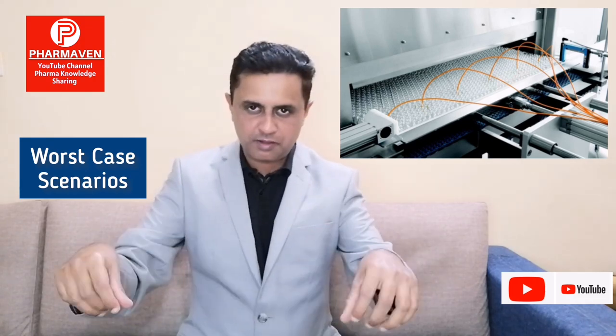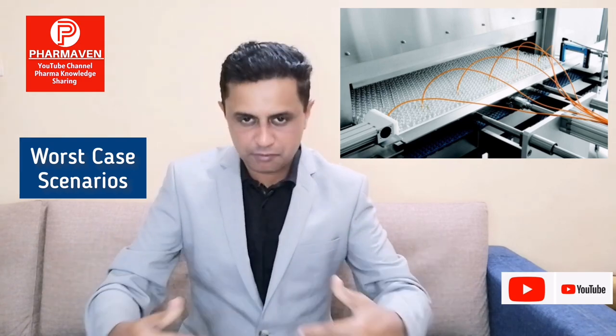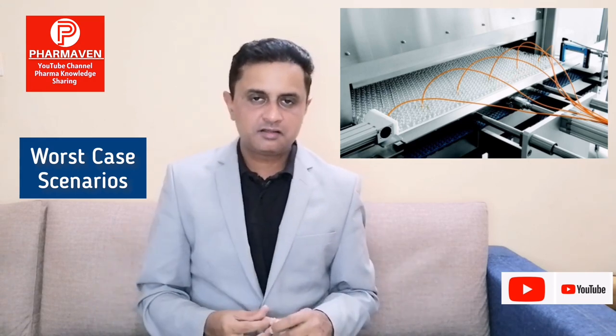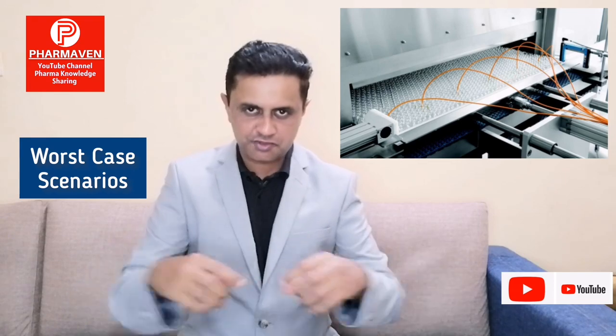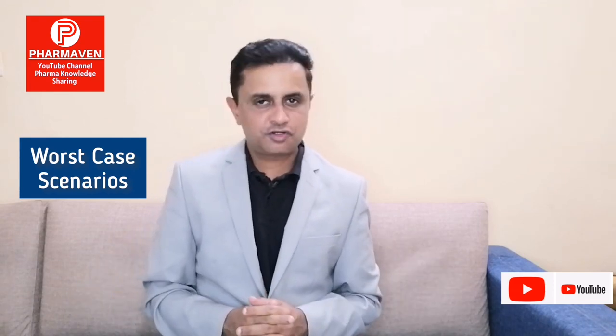So how can it be done? You have to put the sensors inside the vials, allow the vials to pass inside the tunnel conveyor, and gradually release the thermocouple cable so that it will not get pulled or pushed, and it will remain steady at the required place inside the tunnel. So this is how I can measure the initial path, the initial first row, whether it is getting the temperature or not.